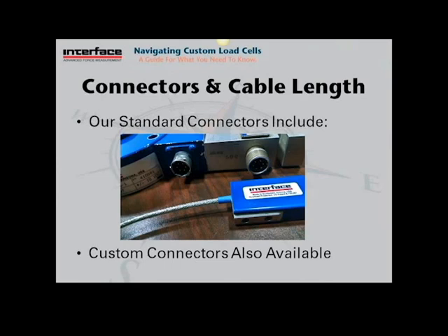Our standard cable that we ship with most of our load cells is non-twisted pair shielded cable. There again, the size and jacketing type depends on the load cell. We also have twisted pair cables available. We have high flex, submersible, and chemical resistant Teflon wrapped cables as well. The lengths of the cables can go anywhere from 1 foot to 500 feet. So we really have a lot of flexibility in that. We design and manufacture all our cables in-house so we can adapt fairly quickly to whatever the customer's needs are.